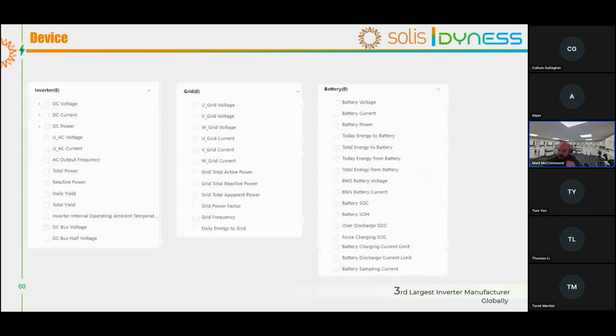Where this does come in use is, if we look at some of the values you can look at, it is to do with inverter, grid, and battery. Inverter means that's information directly given from the inverter to Solis Cloud. The grid is the meter information. So, for example, you could check the AC voltage of the inverter versus the AC voltage measured at the grid. There's stuff like that you can check. And then you have the battery, and this is from the BMS. The BMS is sending this information to our inverter, so we can read values.